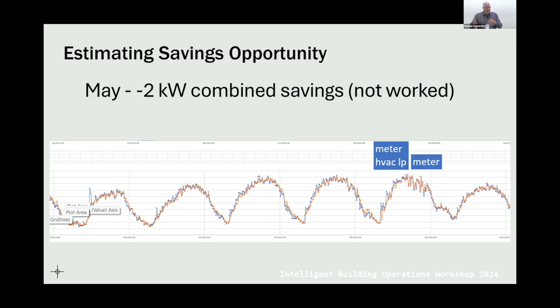Yeah. So that curve smoothing out the HVAC load method is a way to estimate what the load flexibility is, how it could be leveraged in the building in order to distribute the loads. The control algorithm that we used assumes that demand is assessed on fixed 15-minute intervals, so they're discrete intervals. It looks an hour ahead and runs every possible runtime sequence for each of the zones and each of the units. So it'll run on/off for however many units there are, going forward an hour. And then it'll identify the minimum peak occurring in any 15-minute interval.